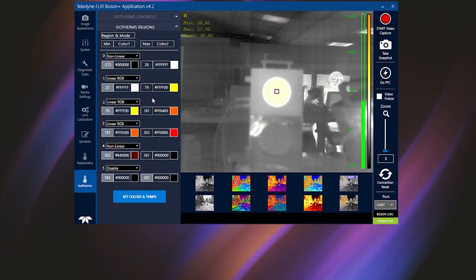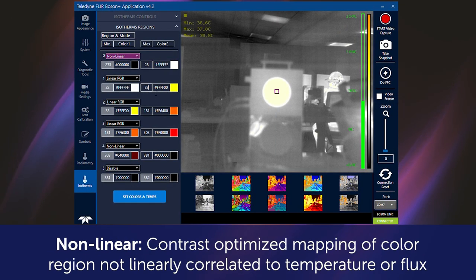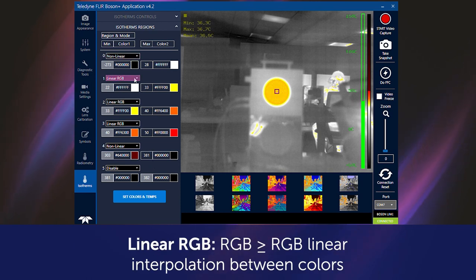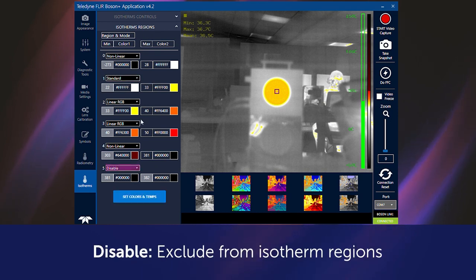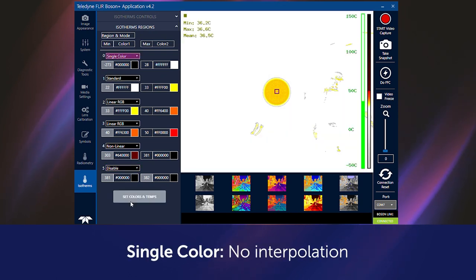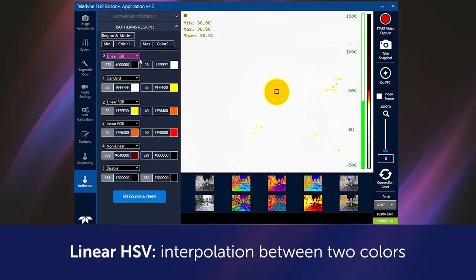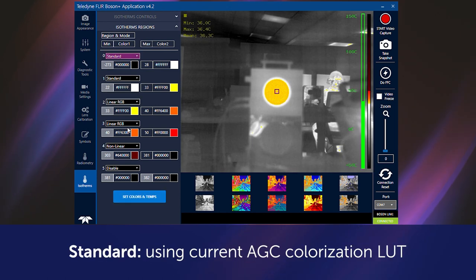For example, utilize low gain mode for high temperature measurements greater than 150°C. In the Boson app, there are 6 regions and modes to help you obtain the right palette: Non-linear (contrast optimized mapping of color, region not linearly correlated to temperature or flux), Linear RGB (linear RGB-to-RGB interpolation between colors), Disable (exclude from isotherm regions), Single Color (only a specified color, no interpolation), Linear HSV (linear HSV color space interpolation between two colors), and Standard (standard AGC output using the current AGC colorization LUT).